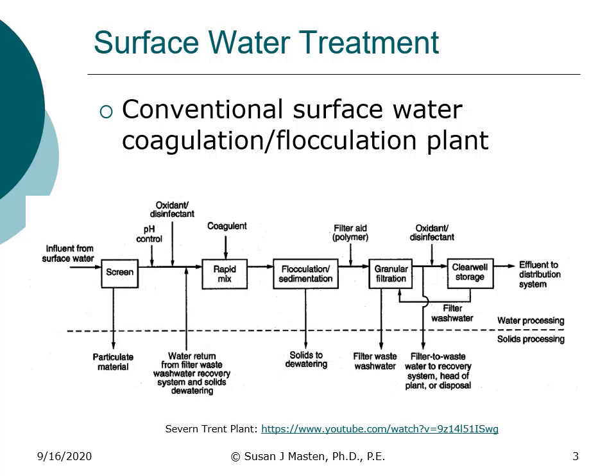It could be for taste and odor control. It could also be as a disinfectant to try and prevent microbial growth in the subsequent processes. You can see here they add a coagulant to the rapid mix system. They then go through flocculation, sedimentation, and then further treatment, which we will talk about extensively throughout the semester.